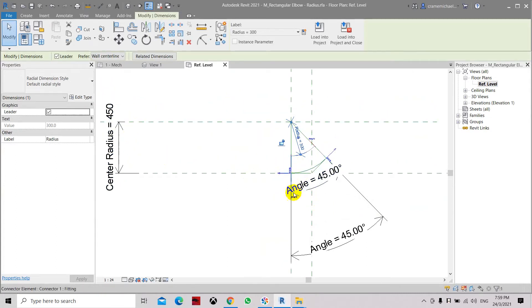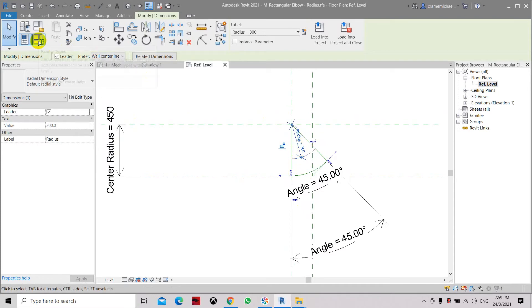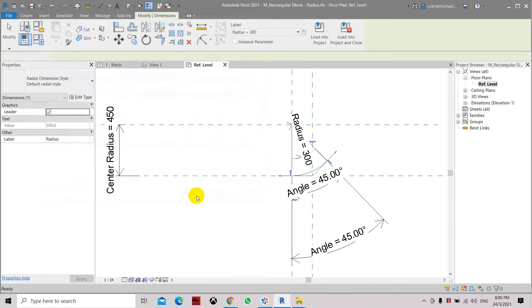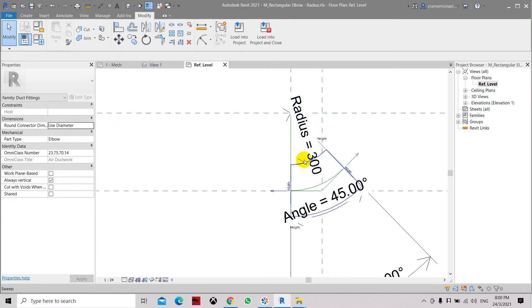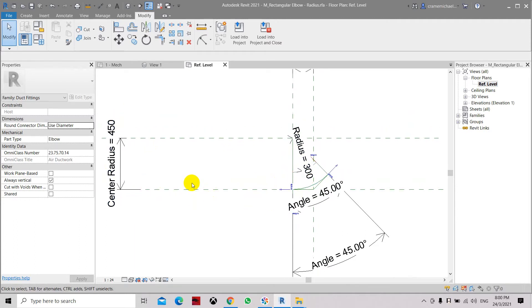This radius needs to reference the center radius, which is driving the width of the center or the center of the elbow. Go to family types again — center radius. We have to replace the radius multiplier with radius. Currently based on 1.5 it's about 300, so let's delete the radius multiplier and add duct width divided by 2, then click apply. So this means 300 plus half of the duct width is the center radius, which is still correct — we just replaced the radius multiplier parameter with the radius.